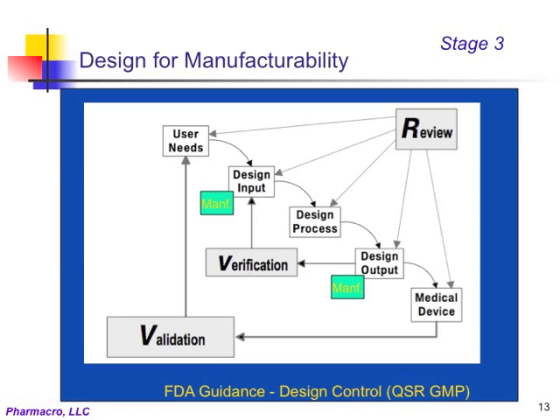This figure is a conceptual presentation of a design development plan including verification and validation. It is part of the FDA's guidance for design control. Essentially, as we have discussed earlier, the user needs are translated into design input or product requirements. The product design output resulting from the development process is then tested against the design input to ensure that the requirements are met. This is referred to as design verification. If the design output does not meet design input requirements, then the design is modified, the specifications updated accordingly, and the modified design is tested again. This cycle is repeated until the design output meets the design input requirements.